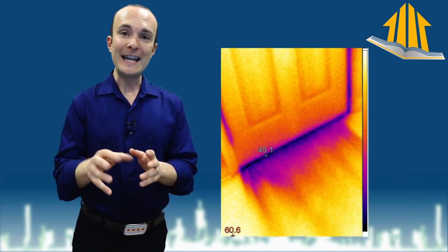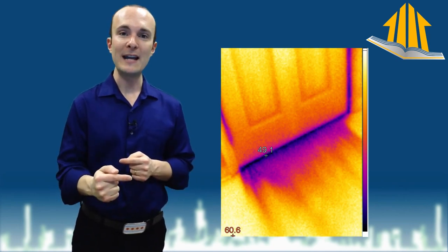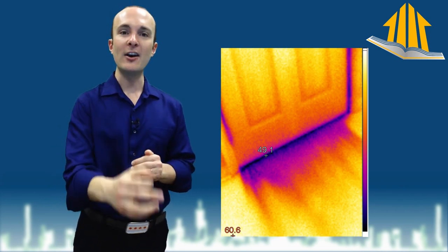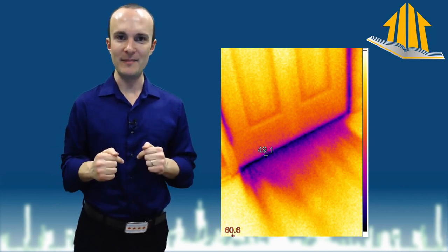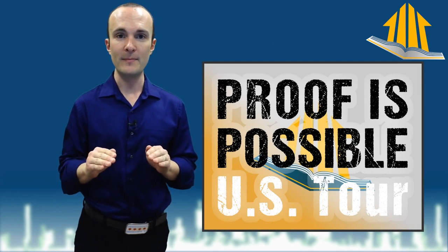Number two, the air in this room is coming out into her unit, not vice versa. So we don't have to worry about warm, moist air making its way into this room. We know for a fact that air comes out of that room and into the apartment. Therefore, we can go ahead and insulate this room with proof that it's not going to be a problem later on.